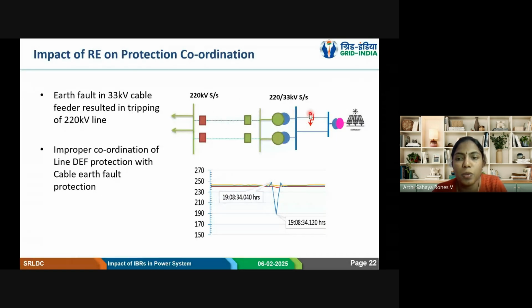So that backup and this overcurrent protection coordination was not done. Because of that, we lost the grid line. So those kind of trippings we had observed, some 3-4 trippings are there. Then coordination was ensured. The pickup and time settings were changed. So this is shown to say that there was no delayed fault clearance. Only when there is a delayed fault clearance, if this is not operated, then the transformer should clear the fault in backup overcurrent. If that also has not operated, then only this 220 kV line is supposed to operate. That also, it should not see this fault because it is not in its direction. So here the non-directional earth fault protection has operated. So it should be directional. So in this case, properly changing the direction, pickup and time settings will avoid the overcurrent protection maloperation. So these kind of coordination issues can be avoided.